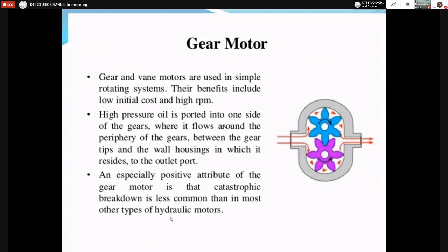In a gear pump, when driving and driven gears rotate in opposite directions, suction is developed at the inlet. Fluid is sucked into the inlet, trapped between the gear teeth, pressure is gradually increased, and finally high pressure fluid is discharged at the outlet. In a gear motor, the principle is opposite to the gear pump: instead of suction at the inlet, high pressure fluid is passed through the inlet. Because of the high pressure, the gear teeth move — both driving and driven gears rotate in opposite directions.